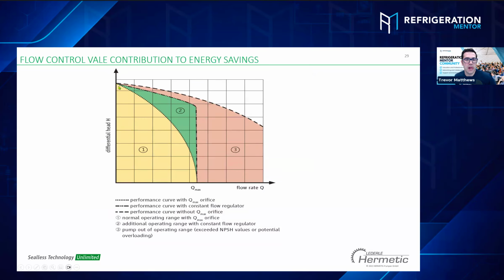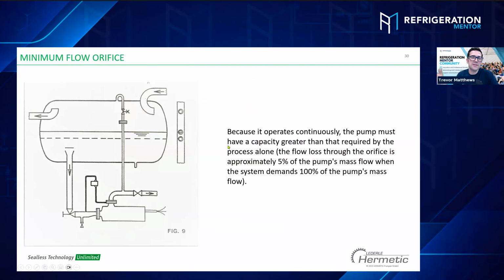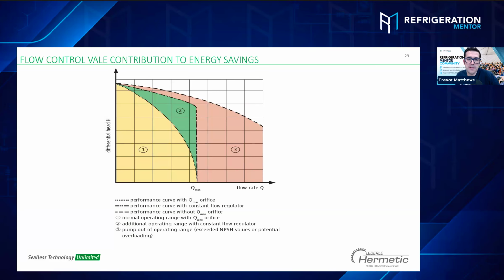This is the chart we have here with the Qmax. You see the curve is decreasing constantly to the max capacity of the pump. This is the regulator. With the regulator we can play more with pressures. And this area is dangerous. You can operate here, but exceeding it is the dangerous area for the pump. This is when you exceed the net positive suction. For example, you require pumping too much liquid, and the vessel starts getting empty because you are pumping in excess of the capacity of the recirculator. You empty the recirculator and the pumps are cavitating.